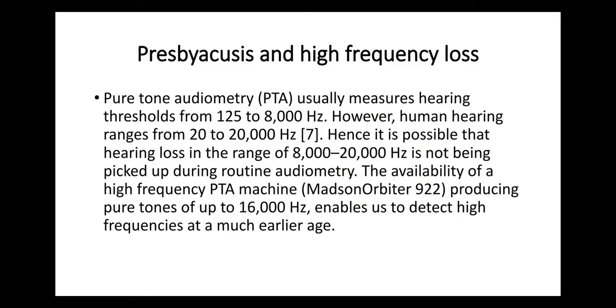Presbyacusis and high frequency loss. A pure tone audiogram usually measures hearing threshold from 125 to 8000 hertz, showing a ski slope pattern to the right indicating high frequency loss. However, human hearing ranges from 20 to 20,000 hertz. Hearing loss in the range of 8000 to 20,000 hertz is not picked up during routine audiometry because most machines do not have this capacity. The availability of a high-frequency PTA machine producing pure tones of up to 16,000 hertz enables us to detect high frequency loss at a much earlier age. Although we say presbyacusis, it usually starts much earlier and can be detected by assessing hearing between 8000 and 20,000 hertz.